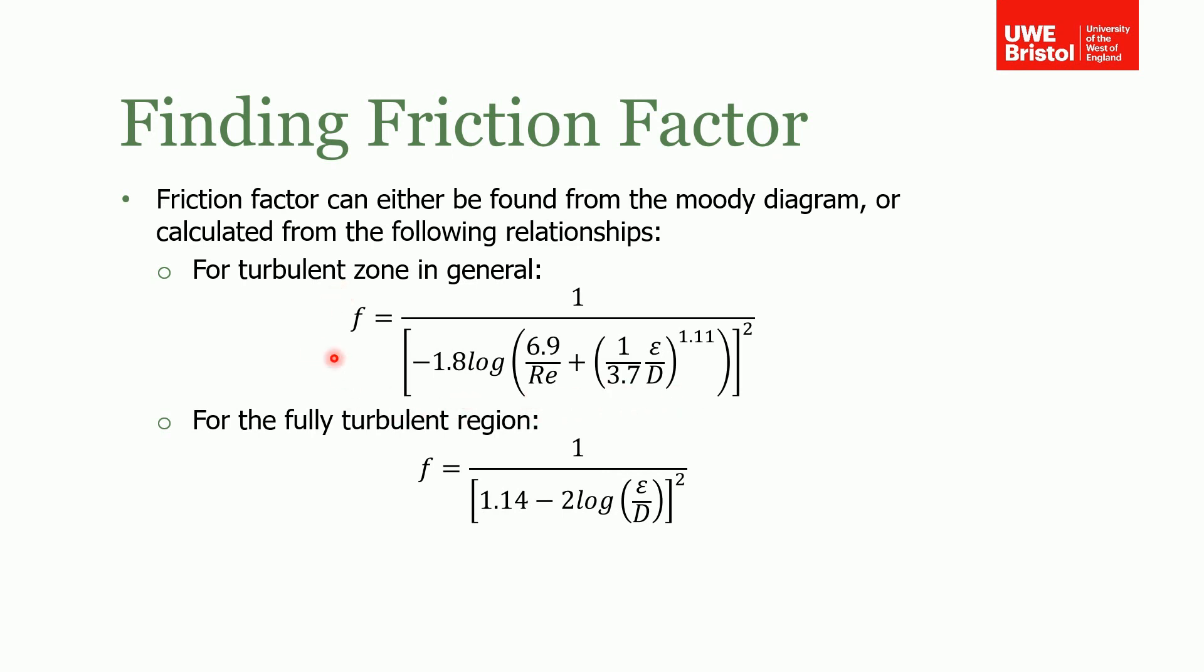In those instances you might be better off using this equation. This is for the turbulent zone in general. The friction factor, I won't read it out because you can see it's a fairly complicated relationship, but the friction factor is equal to this function of Reynolds number and pipe roughness. Basically, this describes the equation for each of those lines on the Moody chart. If you're interpolating between different Reynolds numbers or different pipe roughness, you might be better to use this equation. Notice for the fully turbulent region there is no Reynolds number in here, because of the fact that the friction factor becomes independent of Reynolds number in the fully turbulent region.